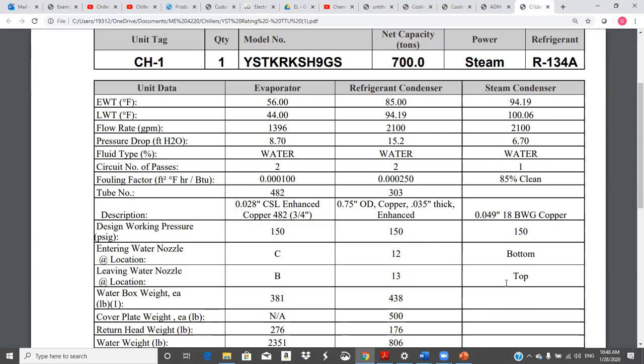Refrigerant condenser, 85 into the chiller, 94 out. So that's our standard cooling tower, 95-degree water into the tower, 85-degree out. And then we also have a steam condenser, because this thing is putting steam into this turbine. What comes out of the turbine may be wet, but it's still a lot of steam, and you don't want to throw that away. So you're going to have to condense the steam out of the turbine that's driving the chiller. Okay, so we got 94 and 100 coming out.